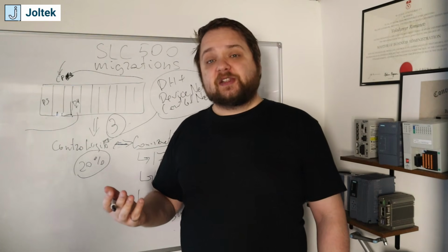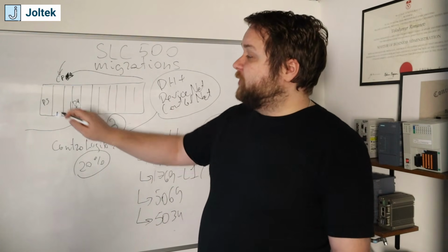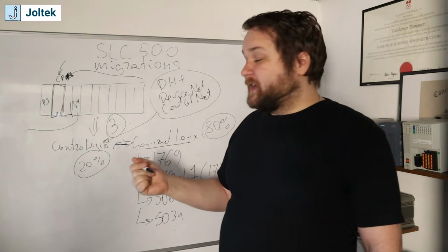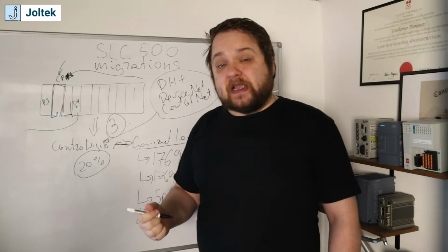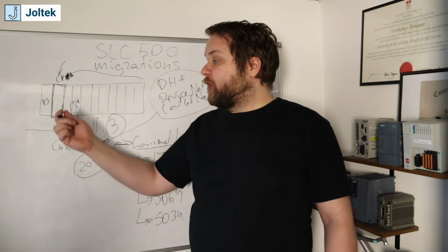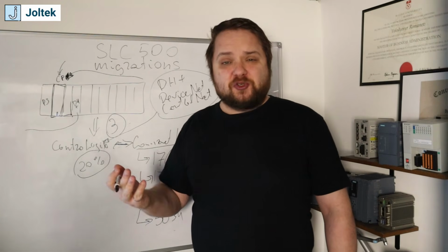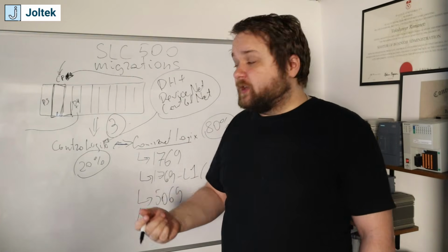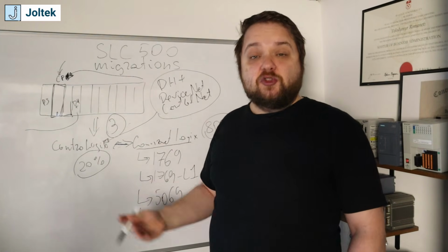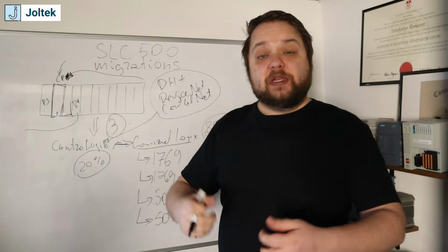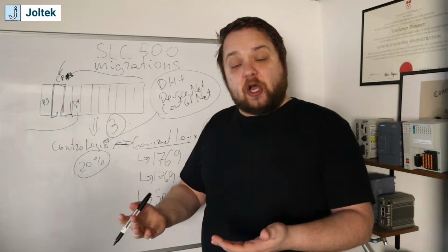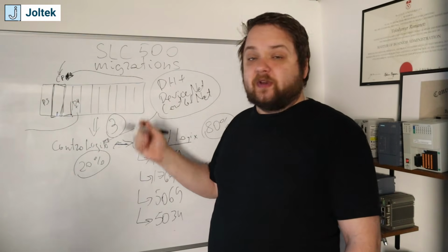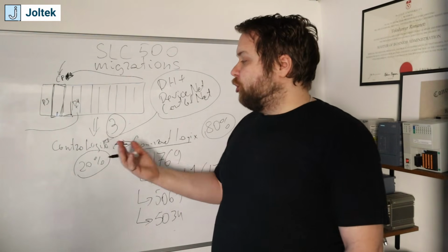Now, going back to scheme number 2, and I can tell you personally that I have made that move for many different customers, it is perfectly acceptable to put in the AENTR card here, move the software to an existing ControlLogix or CompactLogix, and simply have a backup should that rack fail completely, if there are issues, or if you cannot source any more parts, which will probably increase in price over the years, so that if the rack does fail, you have something in your back pocket that you can simply move into. So create a document that would explain the migration in the event of a failure, but it's perfectly fine to leave the I/O as it is in the current rack.